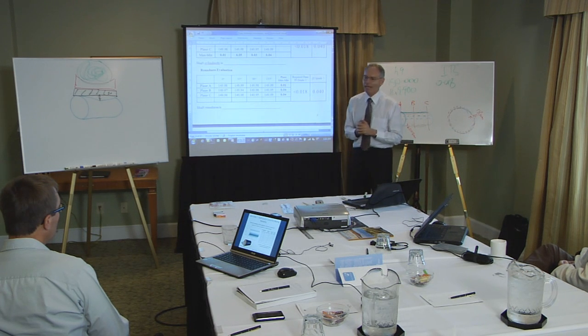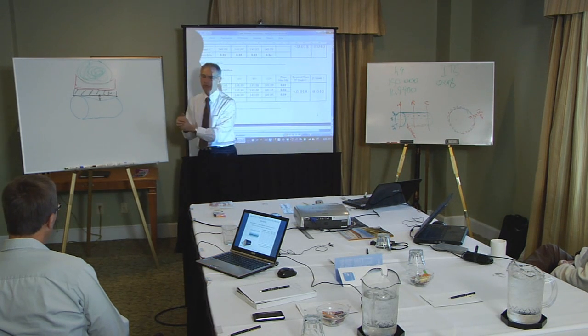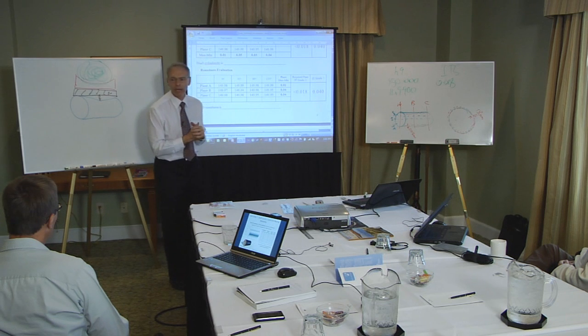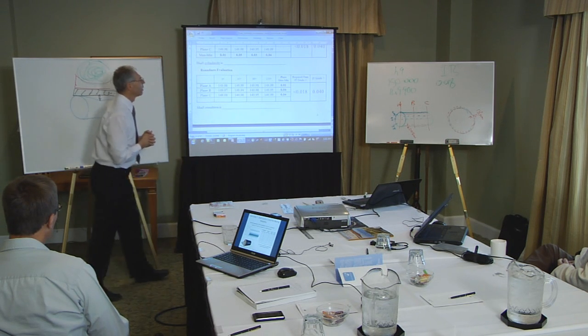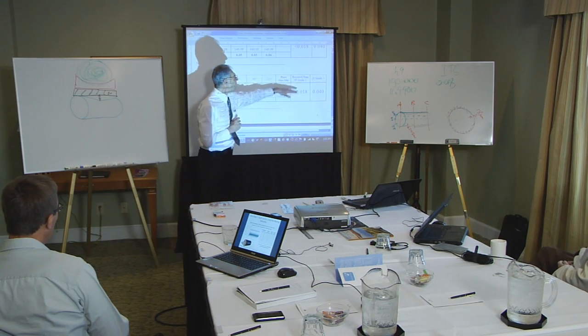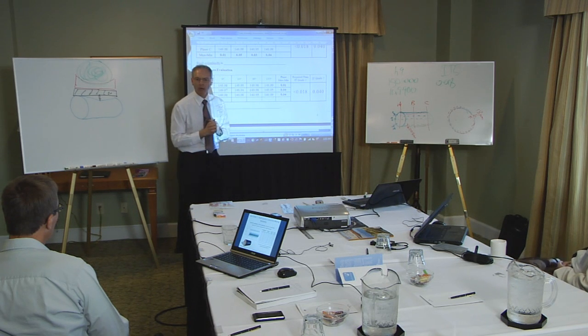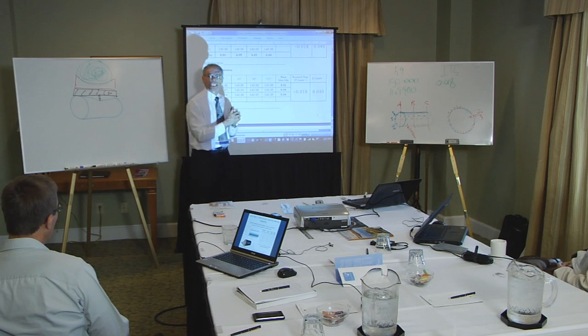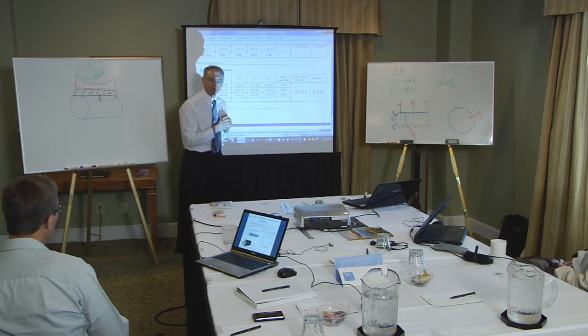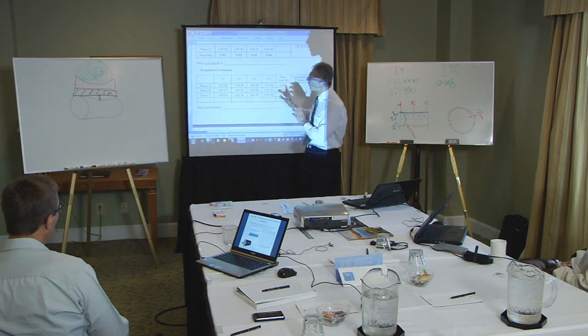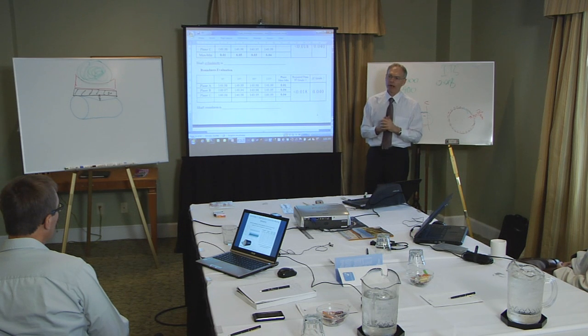After the very first failure, somebody should have measured the shaft to make sure the shaft was round enough to take the bearing. Had they known, hey, got to meet IT5 and got to have H9 tolerance, if that had been in their documentation, if it had been a procedure that says measure the shaft and record the values in this table and compare it against the known acceptable values, we'd have seen it right away, straight away.